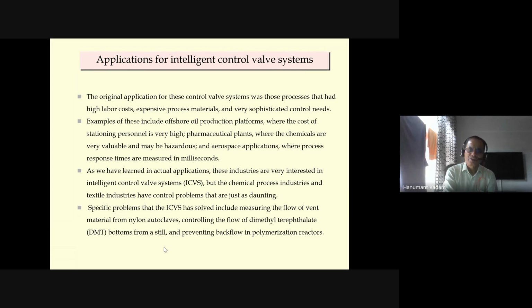Specific problems that the intelligent control valve has solved include measuring the flow of vent material from nylon autoclaves. These are some applications where it was initially launched. Controlling the flow of DMT, dimethyl terephthalate bottoms, these are the refineries, and preventing backflow in polymerization reactors. So if you see here, oil, gas, and pharmaceutical, that is where the applications were initiated earlier.